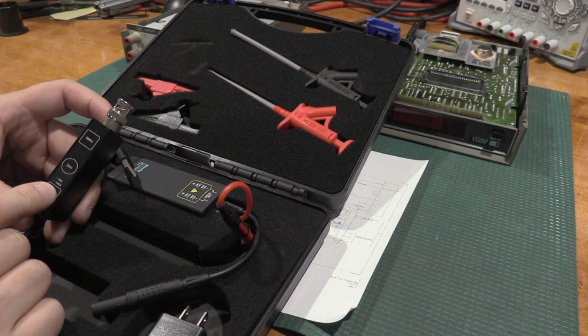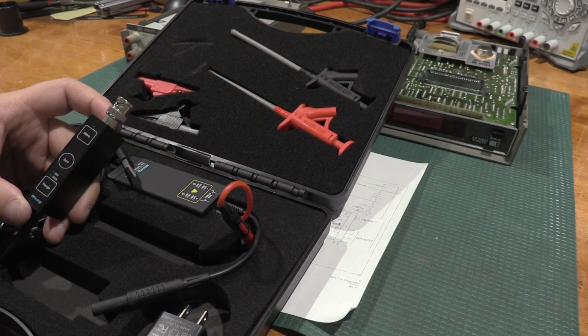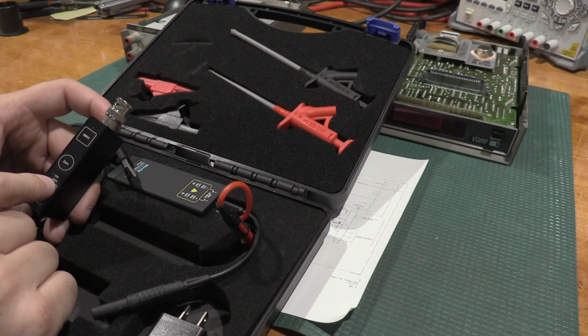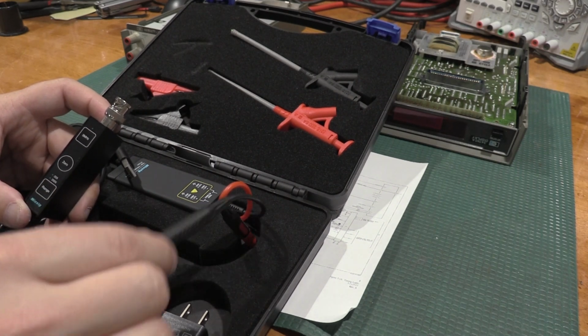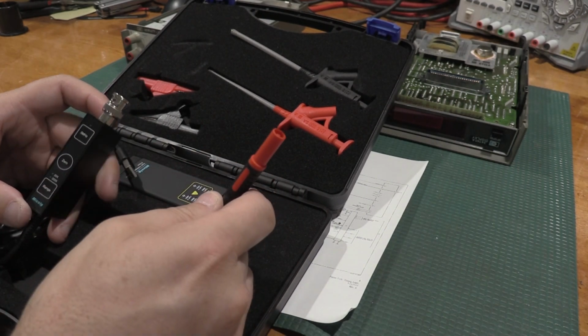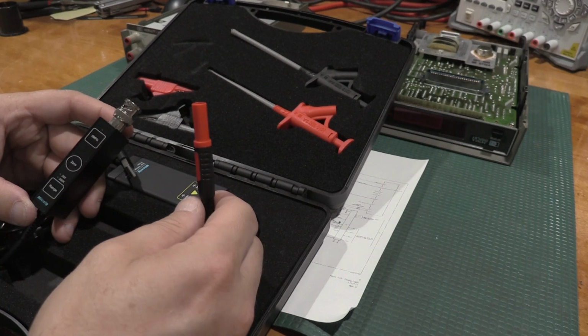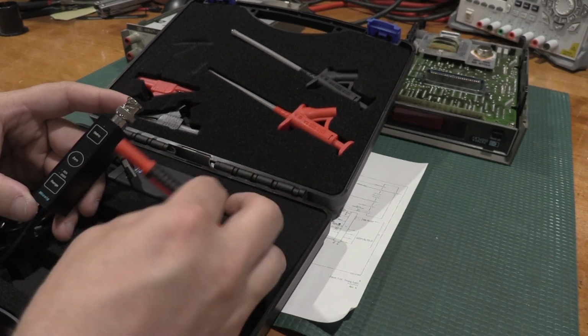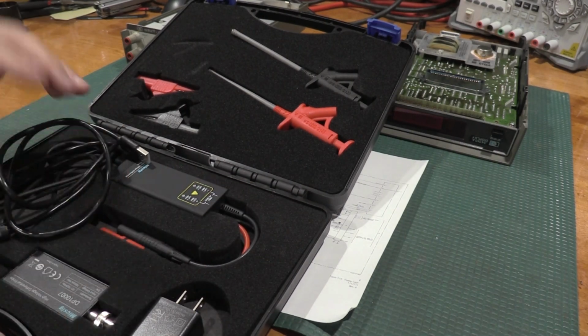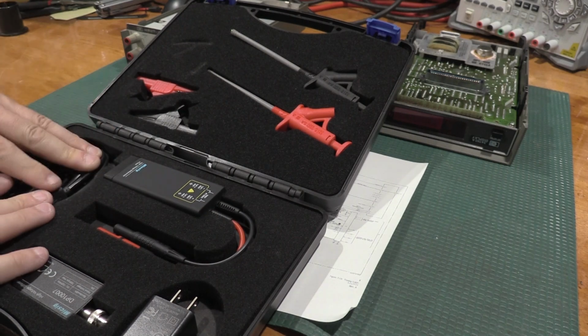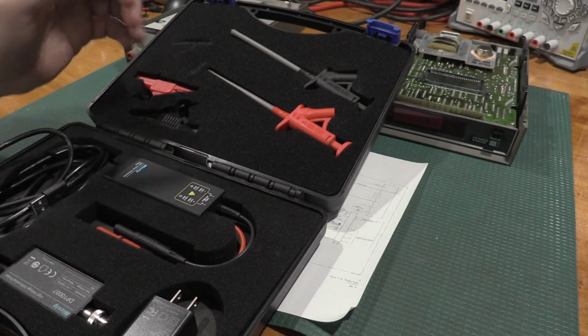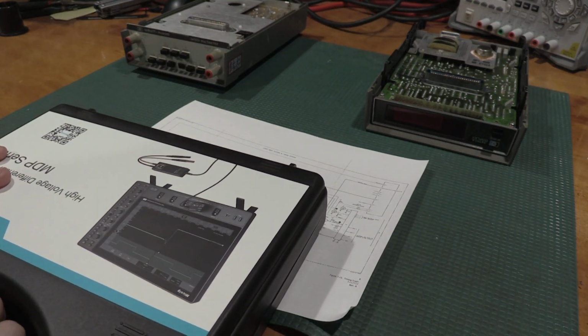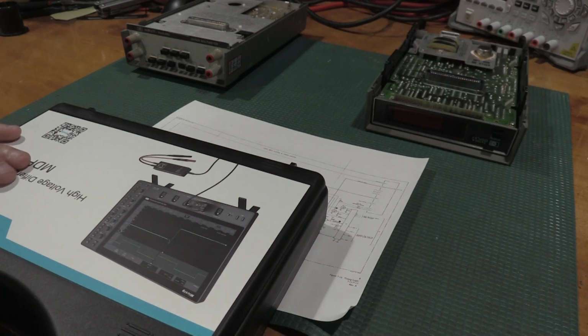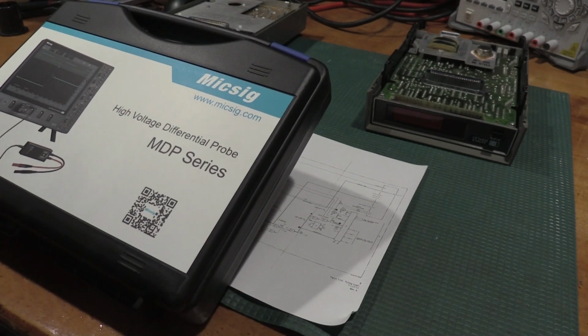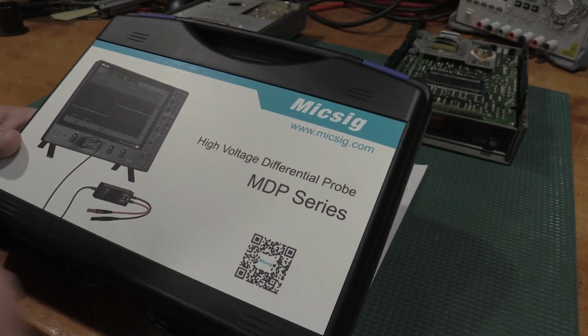Also remember, when looking at these, they are an attenuation factor, not a multiplication factor. So when you set it to 20x, it is a 20 times reduction in signal between here, well, actually here and here. 200x is a 200 times reduction in signal between measurement and scope. So it's how we can extend the range of oscilloscopes well beyond what they're supposed to. There are a couple of scopes that have this capability built in. Most of the time, you'll find they're for heavy industry, essentially panel work. And having a scope with an isolated input is actually fairly rare, and they will spec that.